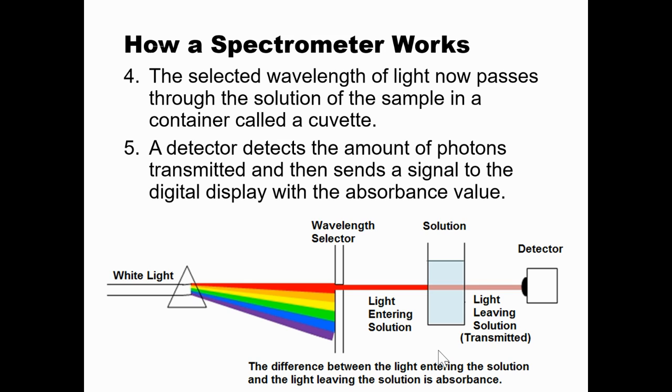Then there's a detector that detects the amount of photons transmitted and sends a signal to the digital display with the absorbance values. Basically, that detector is just a little solar panel, and it records how much light came through by how much electricity it's generating. And that is how a spectrometer works.